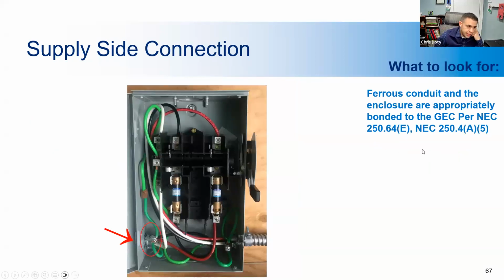So here's another supply side connection. The main difference here is that there's no bare ground conductor. The ground is run via the green conductors, which obviously all have insulation on them, and you can see it crimped together on the left-hand side. So this is done. The NEC requires that this enclosure and the conduit be bonded at both ends, if run in ferrous conduit, which is metallic conduit.